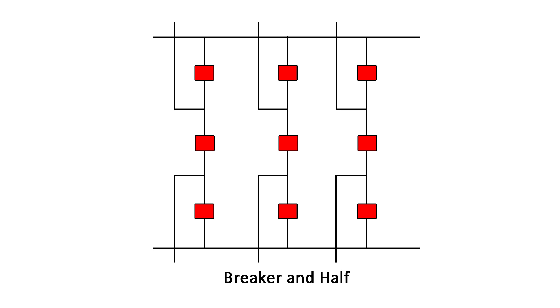Think of it as: to control one circuit requires one full-and-a-half breaker. The middle breaker is shared by both circuits, similar to a ring bus scheme where each circuit is fed from both sides.